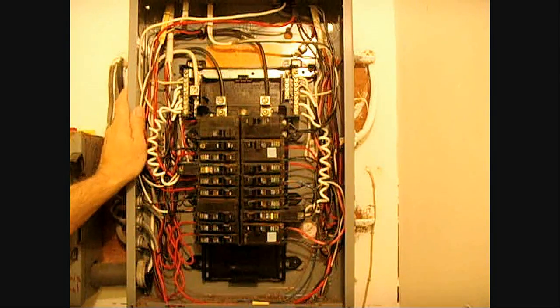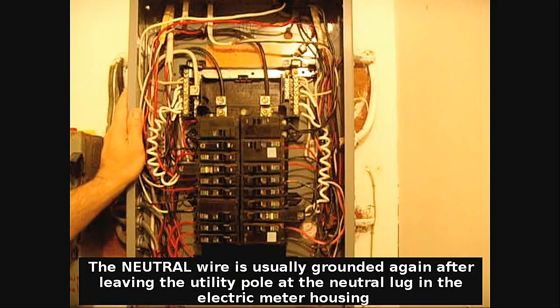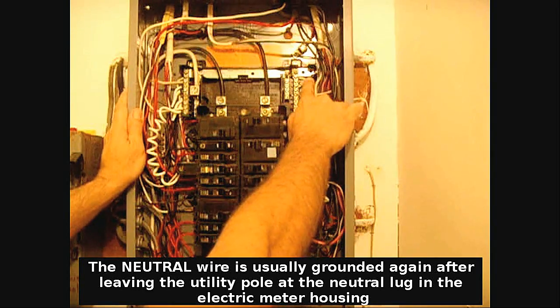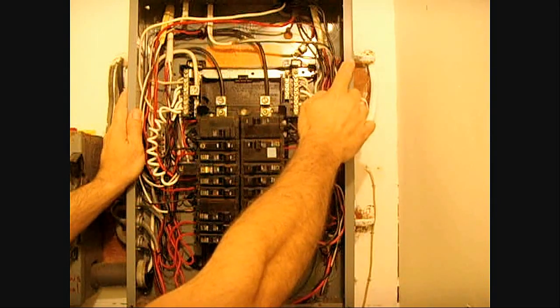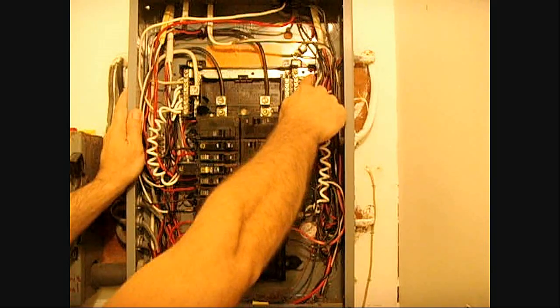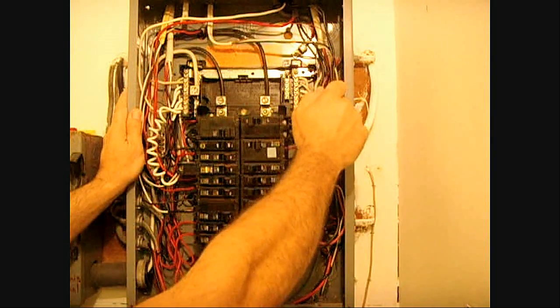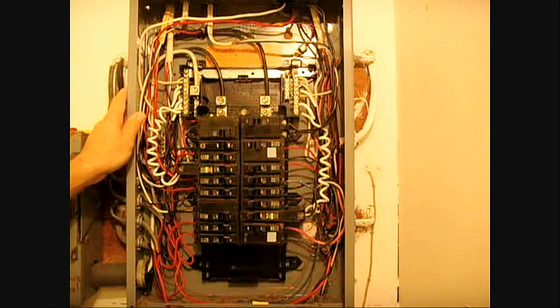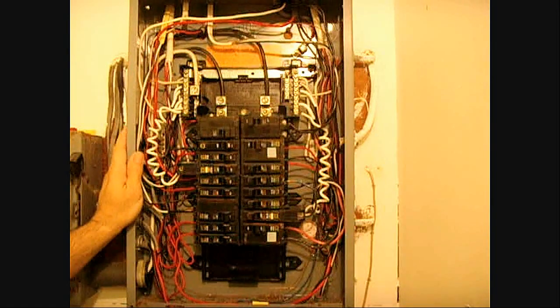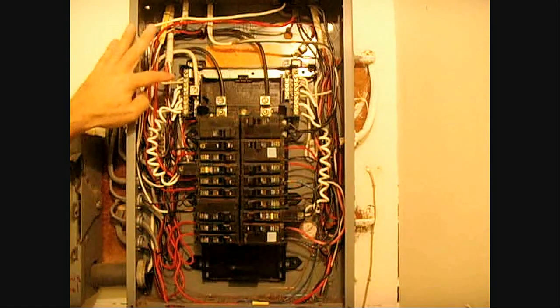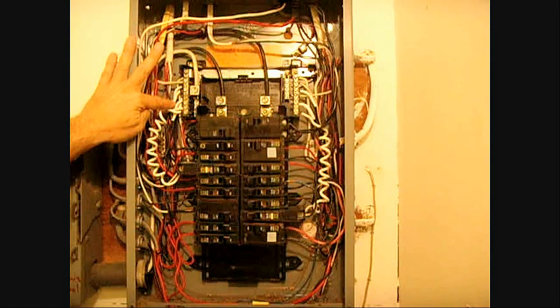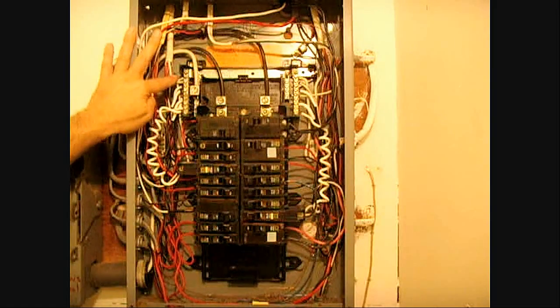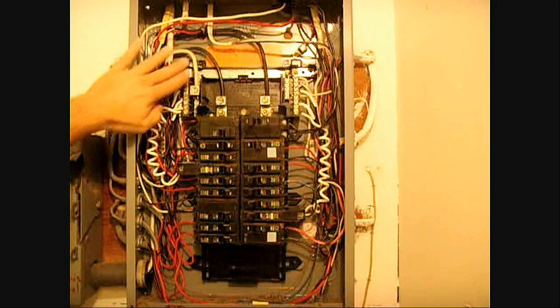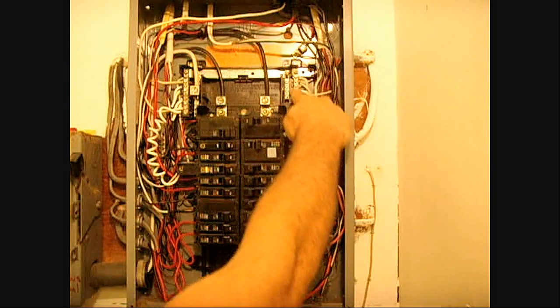Now in order to connect this to the enclosure, which would basically be the ground, just like on the utility pole how it's grounded, there's two holes. Through those two holes there is a threaded hole on the enclosure. You would place a bolt right there and tighten it in securely, and what you would be doing is taking the neutral and bonding it to the panel, making the panel also neutral. When that is done, you normally would take all your white wires, which is your neutrals or your grays, and your bare wires or your green wires, and they all would be connected to these terminals you're looking at right here.